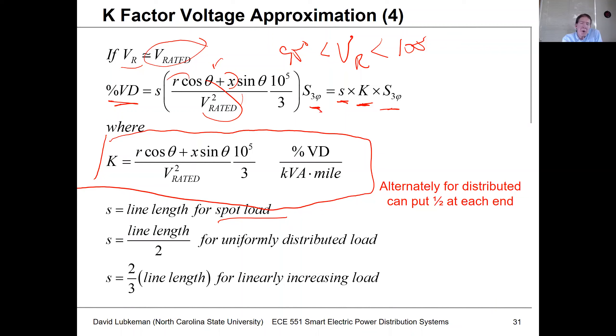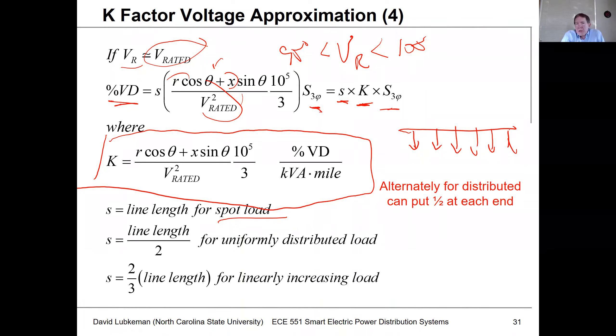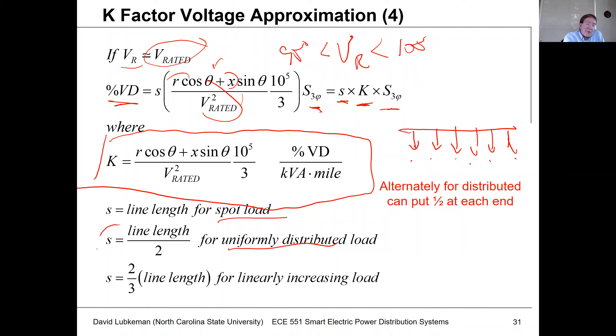There are many cases where we don't have all the load right at the end of the line — it's actually broken down along the entire line length. A lot of times we make what's called a uniformly distributed load assumption, where the load is broken into smaller loads distributed up and down the length of the line. In that case, we won't get as much voltage drop because the load is spread out instead of all being at the end of the feeder. For a uniformly distributed load, the equivalent value of S is the line length divided by two.